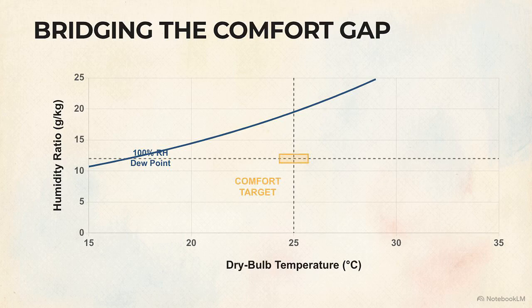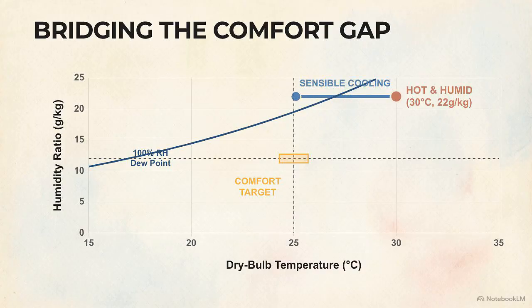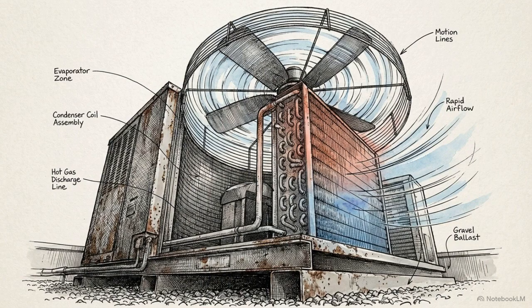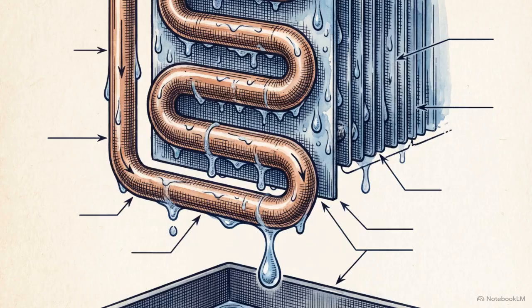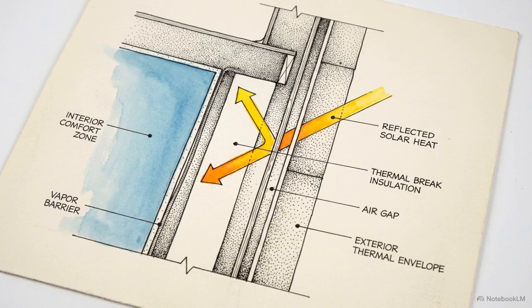kilogram. In standard buildings, cooling starts at a hot, humid state, like 30 degrees and 80% relative humidity, and pushes leftward toward that target. Because the sensible load is massive, the compressor runs continuously. It wrings out the indoor moisture by accident, a process known as dehumidification by chance. In a low SHR passive house, the context changes entirely. The sensible load is near zero.